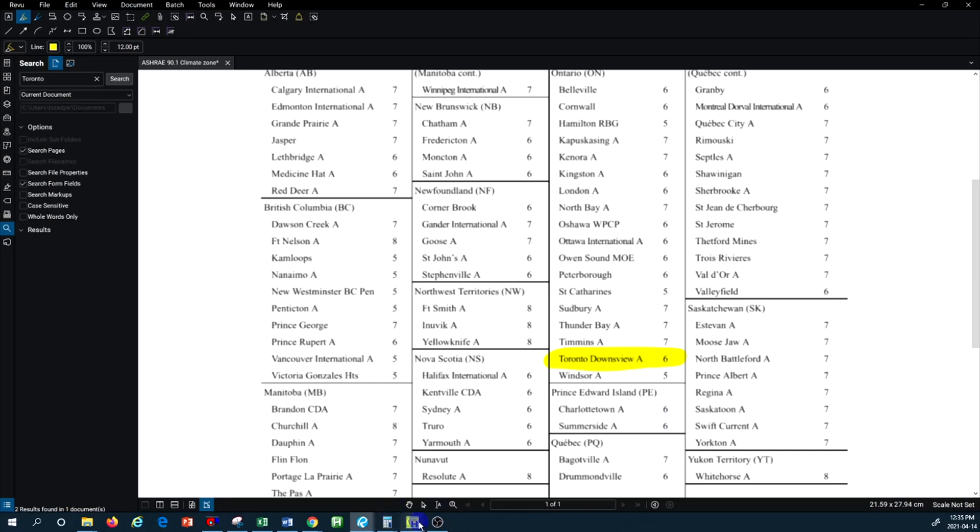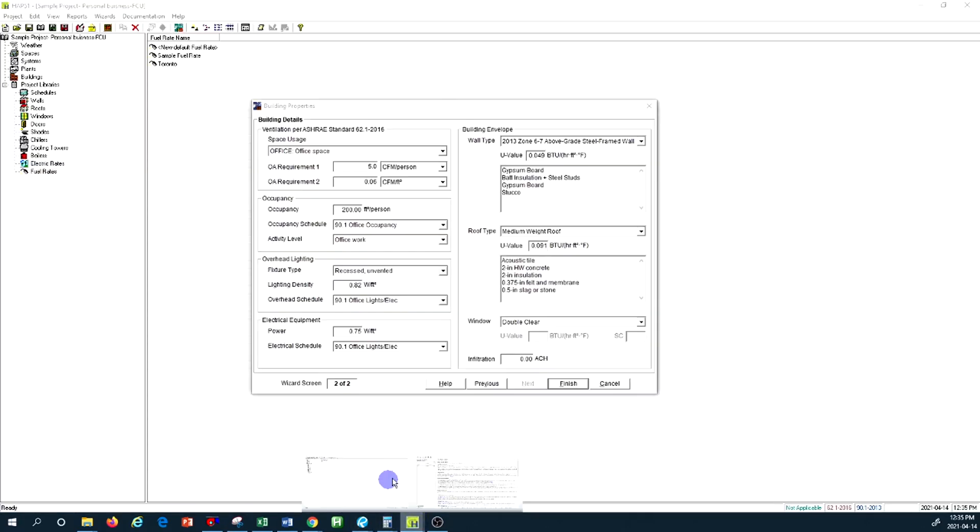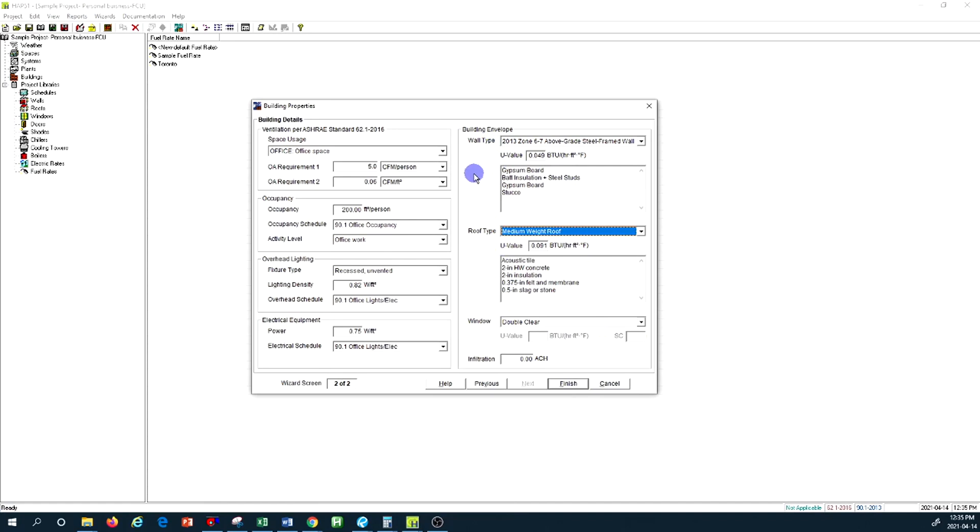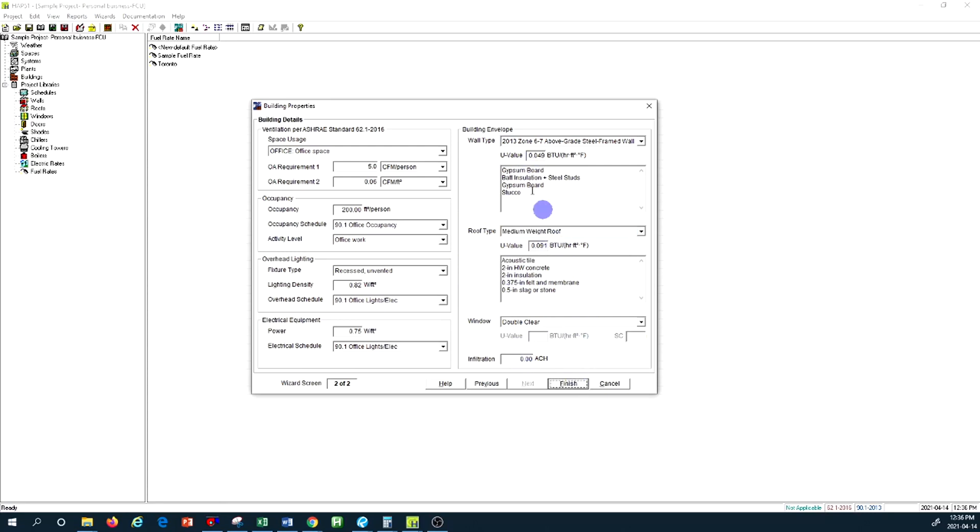So this is the zone and that's the city, so you know that. And then based on this you can select your wall membrane heat transfer rate or U-value which is the rate of heat transfer in the building envelope. So you have wall, roof, and window.